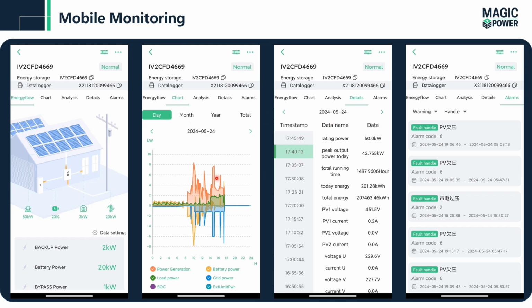The next one, if we further move into the details, we choose the date and the time slot. In that we can see the rated output or generation power for the batteries, the battery voltages, the PV voltages, the power grid voltages. And for the battery we can also see the state of charge, state of health of the battery, current of the cells, and voltages of the cells. And the main thing is temperature for our energy storage system. The next thing is alarm for the system.